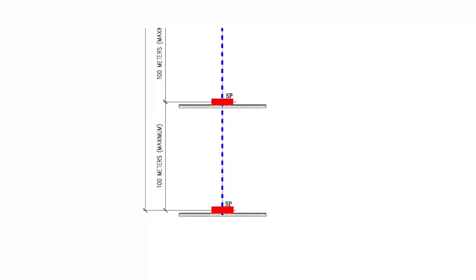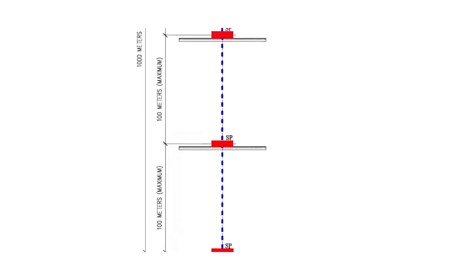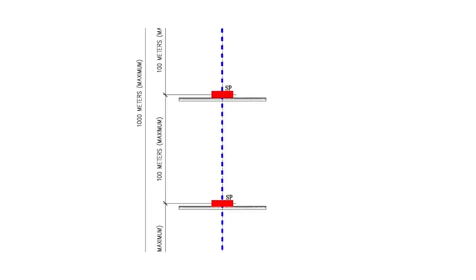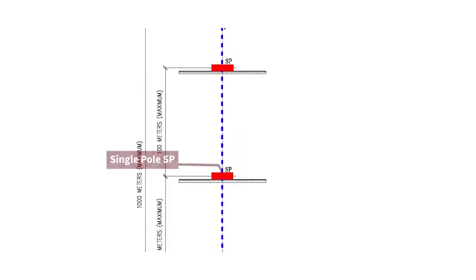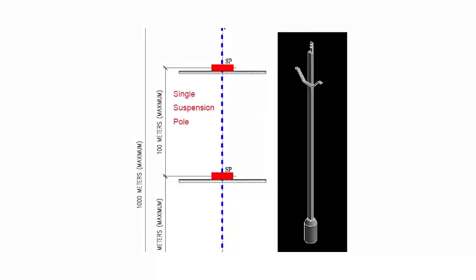To start with, we will try to see the drawing which is being shown on the screen. The red one indicated in the drawing is a simple pole, a single pole, and the longer one indicates the cross arm. For clarity, we have not provided the detail of the top cleat. All these 3 poles which are showing are single pole suspension poles, and the maximum span as approved by the existing line authorities is 100 meters, provided it is a straight line.